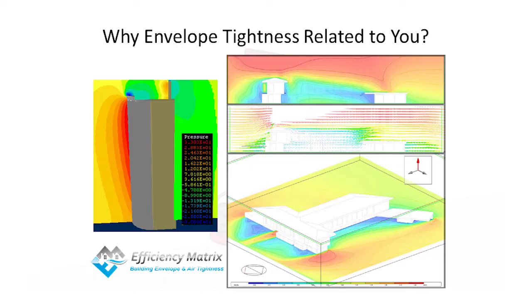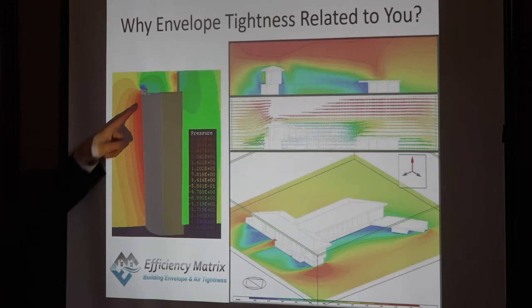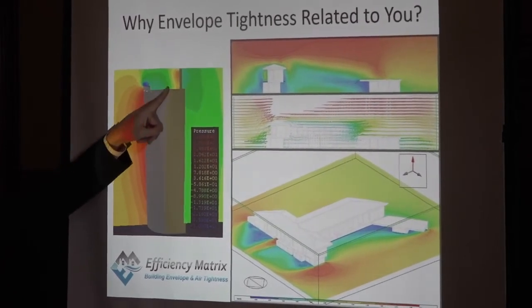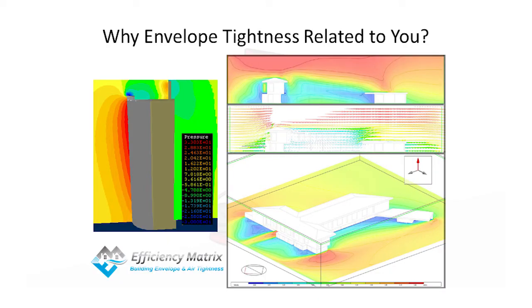These CFD diagrams show significant pressure differences between different sides, facades, and heights of the building. If you don't seal the building properly, your indoor space — especially perimeter zones — will follow the pressure outside. Imagine a very high pressure acting on the facade while your air handling unit sits on the roof where the Venturi effect creates suction. On some windy day, the fan may not be able to overcome both the suction and the pressure pushing back from inside.